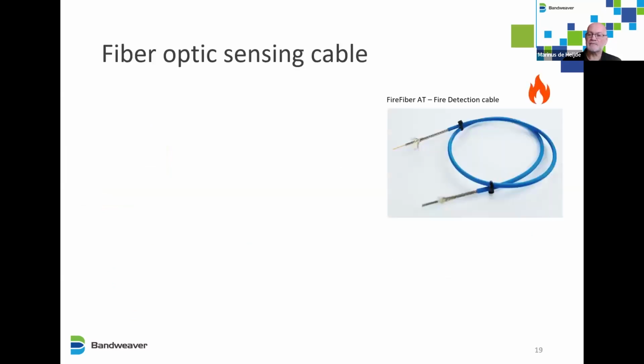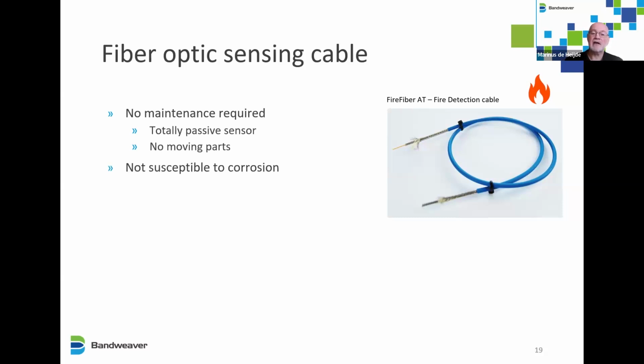So the cable itself is an AT cable, where AT stands for armored tube. It's got a metal covering and also Kevlar, so it's a very strong and robust cable. There's no maintenance required. It's a totally passive sensor, which makes it suitable for industrial installations. There are no moving parts, only a laser going through it, and it's not susceptible to corrosion. The design lifetime is over 30 years.